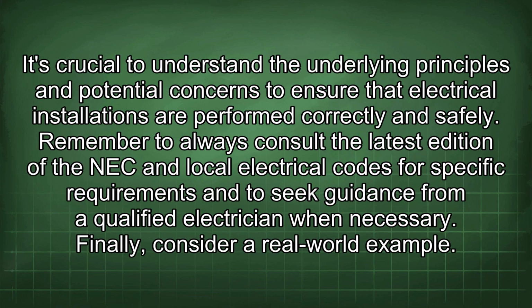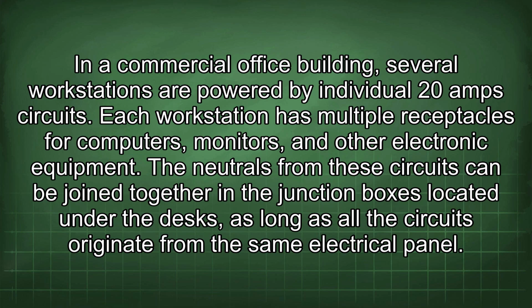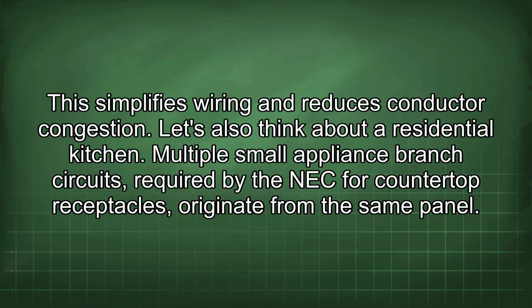It's crucial to understand the underlying principles and potential concerns to ensure that electrical installations are performed correctly and safely. Remember to always consult the latest edition of the NEC and local electrical codes for specific requirements and to seek guidance from a qualified electrician when necessary. Finally, consider a real-world example. In a commercial office building, several workstations are powered by individual 20-amp circuits. Each workstation has multiple receptacles for computers, monitors, and other electronic equipment. The neutrals from these circuits can be joined together in the junction boxes located under the desks, as long as all the circuits originate from the same electrical panel. This simplifies wiring and reduces conductor congestion.